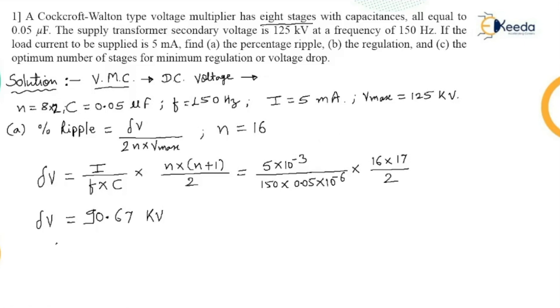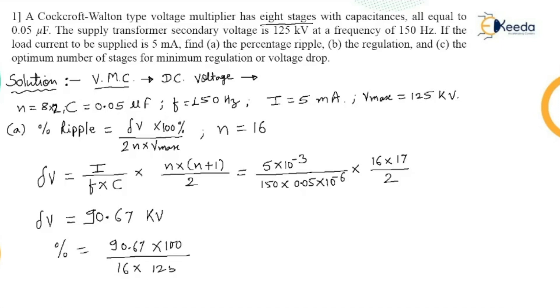Now percentage ripple can be calculated. Percentage ripple equals delta V into 100, divided by 2N into V_max. Delta V is 90.67, multiplied by 100, divided by 16 multiplied by V_max of 125 kilovolt. This comes out to be 4.53 percent. So this is our first value: percentage ripple equals 4.53%.